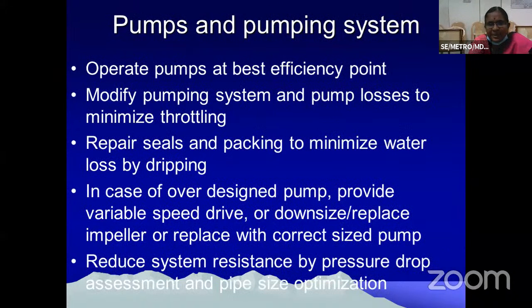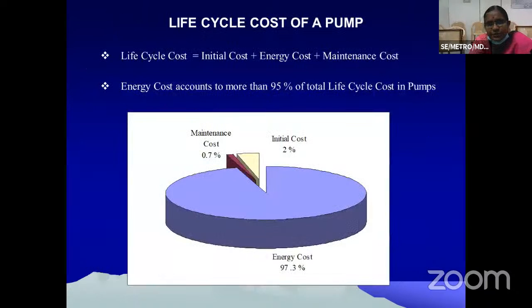Pumping systems, where you can make some modifications: operate the pumps at best efficiency point, modify the pumping system and pump losses to minimize throttling, repair seals and packing to minimize water losses by dripping. In case of over-designed pumps, provide variable speed drives or downsize, replace the impeller or replace with a correctly sized pump. Reduce system resistance by pressure drop assessment and pipe size optimization.